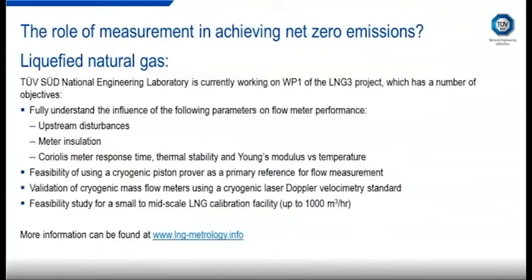Within this project, NEL are working on Work Package 1 in the LNG3 project. This has a focus on the effect of upstream disturbances and meter insulation on the measurement results from the flow meters tested. There's also a focus on the Coriolis meter response time, thermal stability, and the effect of temperature on Young's modulus, and ultimately the flow meter error. We also investigated and demonstrated the feasibility of using a cryogenic piston prover as the primary reference for the flow measurement. And there were additional measurement techniques studied, including laser Doppler velocimetry for verification of the flow meters.